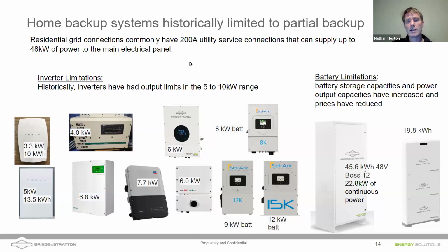But most of the inverters haven't had this capability to back up a reasonable enough proportion of that 200 amp service to really do whole home backup. Now, keep in mind, whole home backup doesn't mean that we're providing 200 amps worth of service on the panel. It does mean that we are putting all of the loads on that panel onto the Sol-Ark. And one of the nice things about the Sol-Ark 15k is you get 200 amps of pass-through. That means you don't have to run a separate critical loads panel. You don't have to parallel systems. You can simply pass all of that 200 amps worth of service through the inverter to the loads.